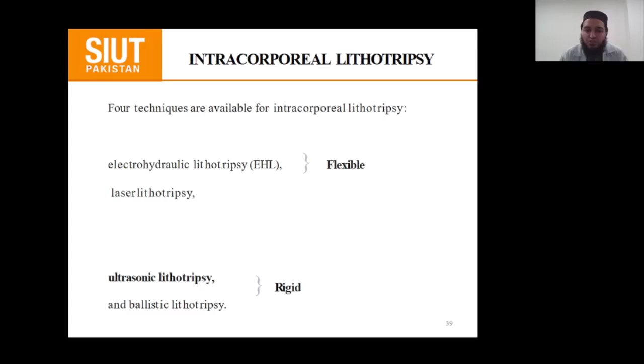Electrohydraulic lithotripsy mechanism. The first technique developed for intracorporeal lithotripsy was electrohydraulic lithotripsy. A high voltage applied across a concentric electrode underwater generates a spark. This vaporizes water, and the subsequent expansion and collapse of the gas bubble generates a shock wave. The shock wave is not focused, so the electrohydraulic lithotripsy probe must be applied within 1 millimeter of the stone to optimize the stone fragmentation. So this electrohydraulic lithotripsy mechanism is most commonly used in the fragmentation of the bladder calculi, as there are more chances of trauma to the urothelium, so it's not a preferred option for ureters.